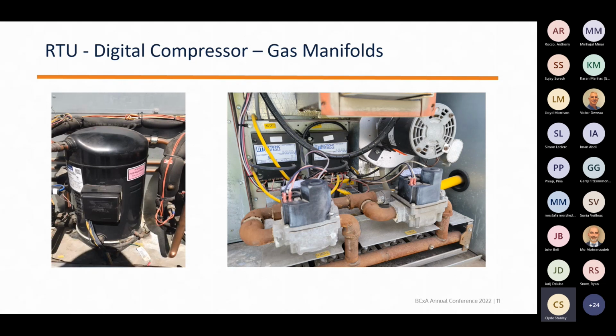This system was commissioned quite some time ago, and we come across these problems. And these gas valves, here's another example, these are two manifold gas valves. When you're commissioning a unit, it's important to make sure you've got your manifold pressures right. Check your inlet gas pressures on low, high fire. Make sure you got the right manifold required pressure for efficient operations.